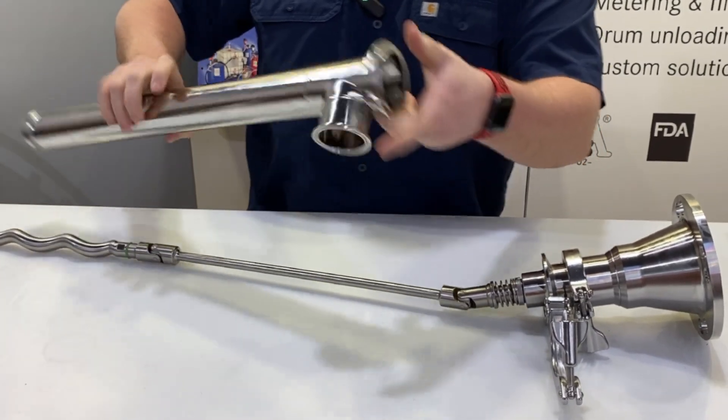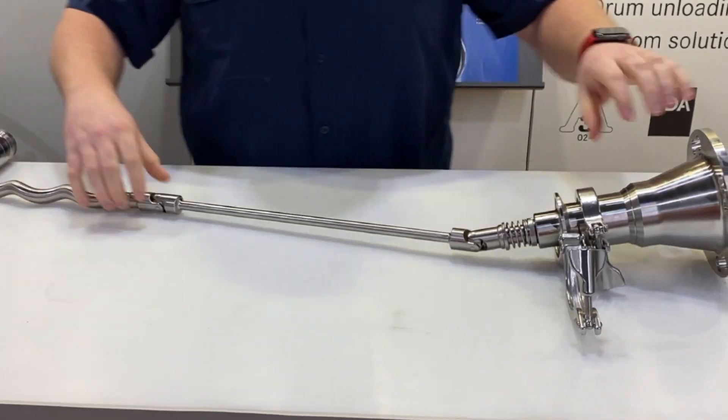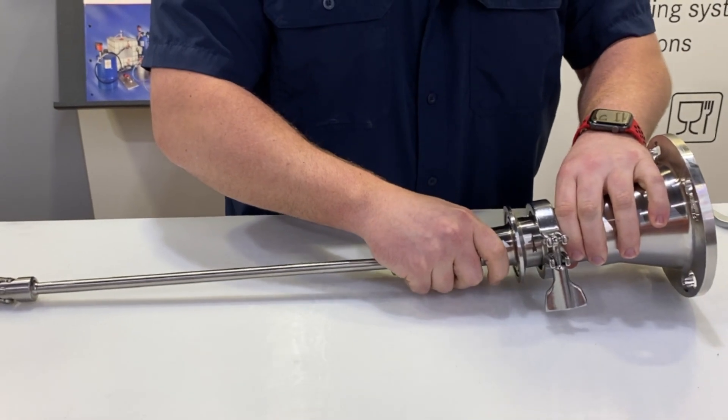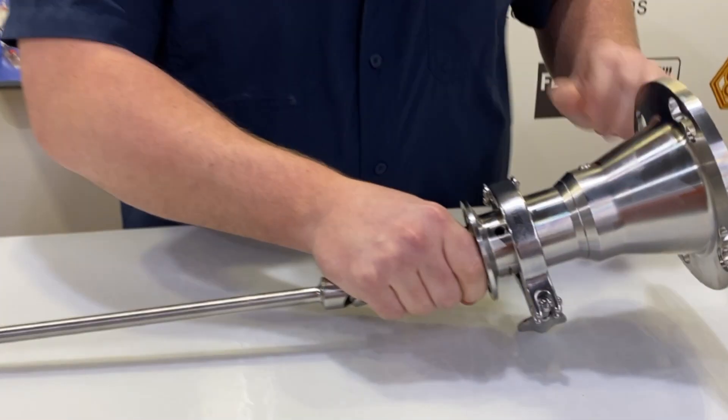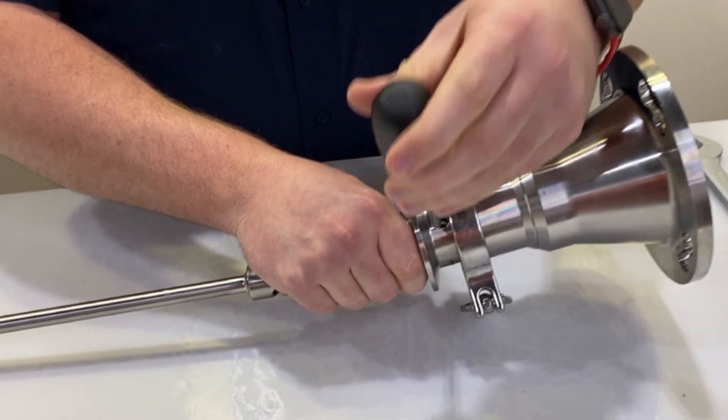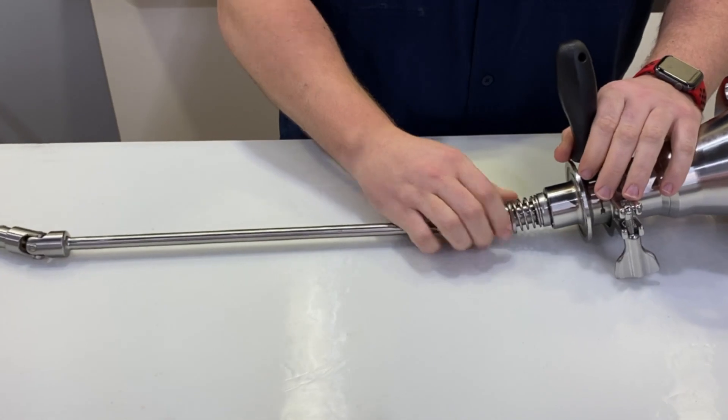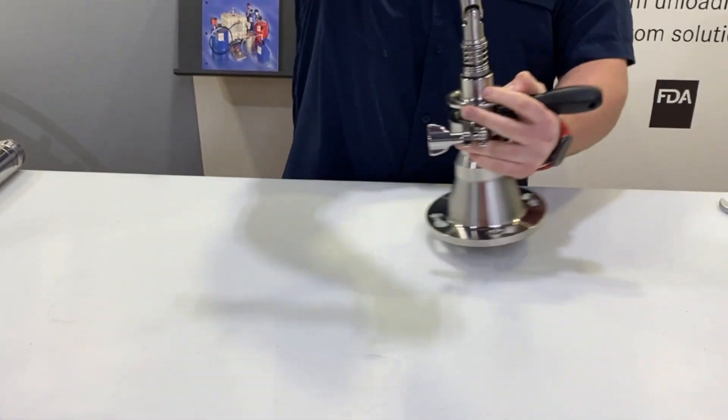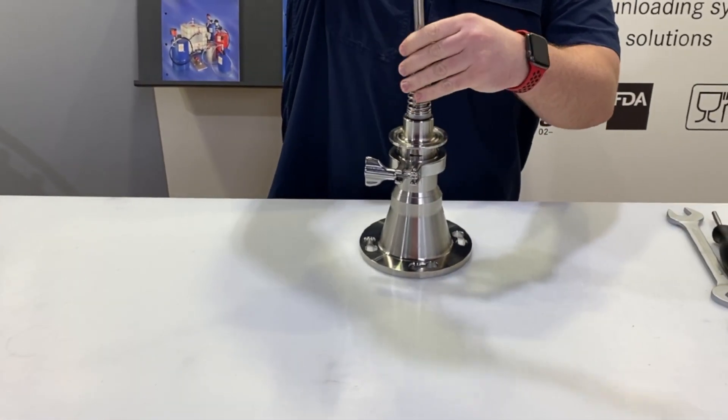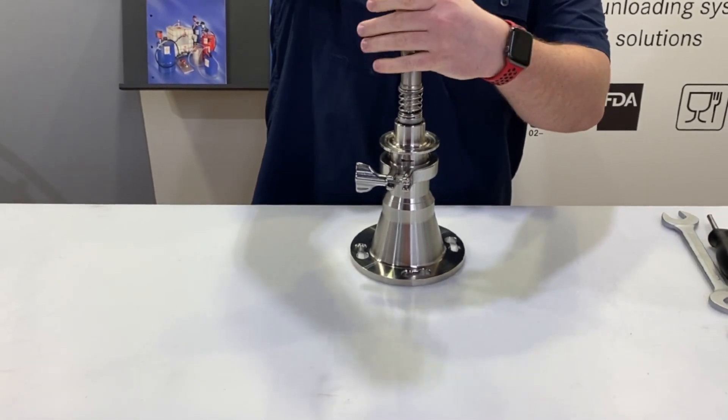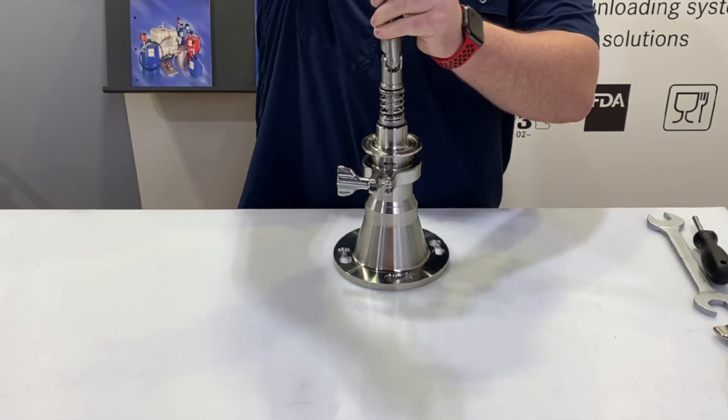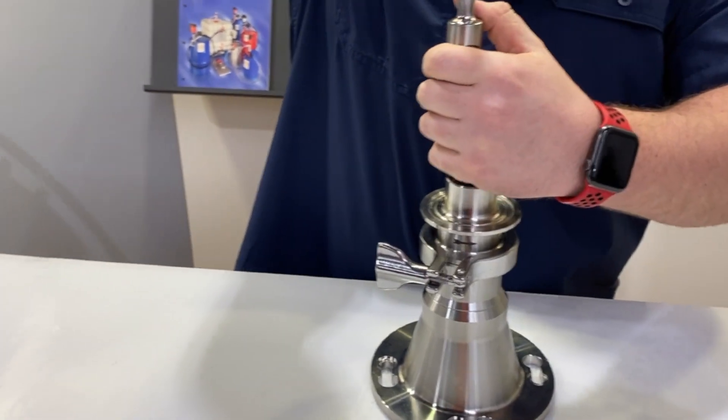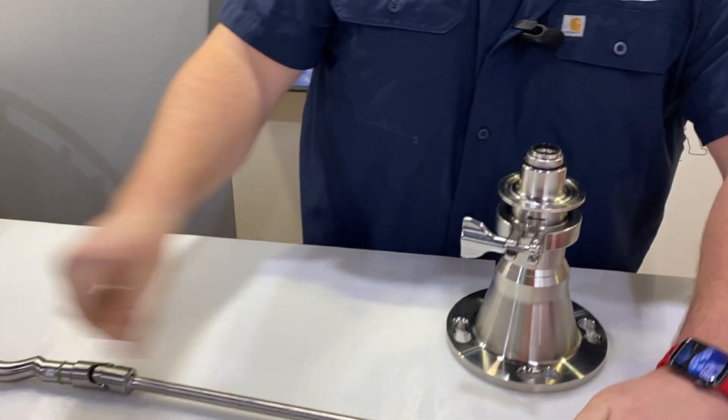We'll then remove the shaft from the bearing housing. You do that by aligning these sight windows and inserting your staking tool to keep that shaft from rotating, and then just break the shaft loose and thread the shaft off of the bearing housing.